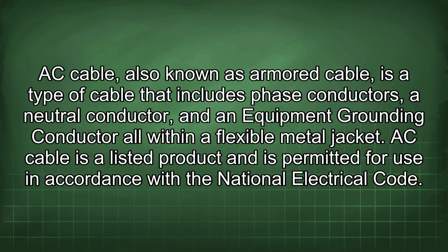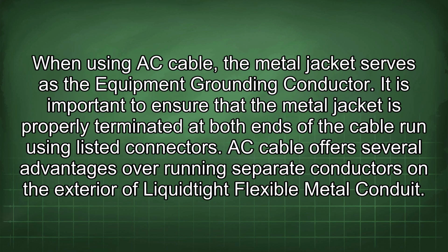AC cable is a listed product and is permitted for use in accordance with the National Electrical Code. When using AC cable, the metal jacket serves as the equipment grounding conductor. It is important to ensure that the metal jacket is properly terminated at both ends of the cable run using listed connectors. AC cable offers several advantages over running separate conductors on the exterior of Liquidtight Flexible Metal Conduit.